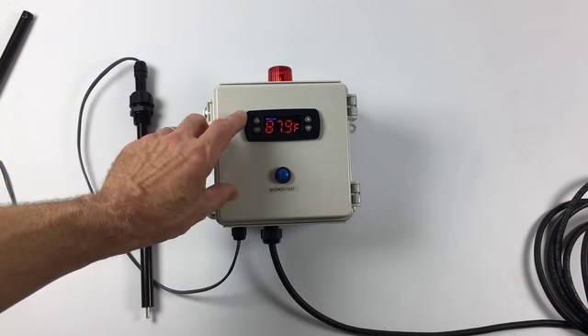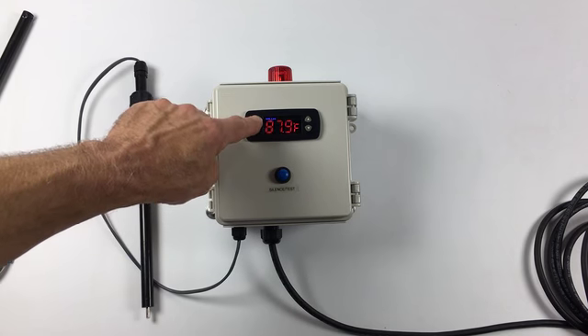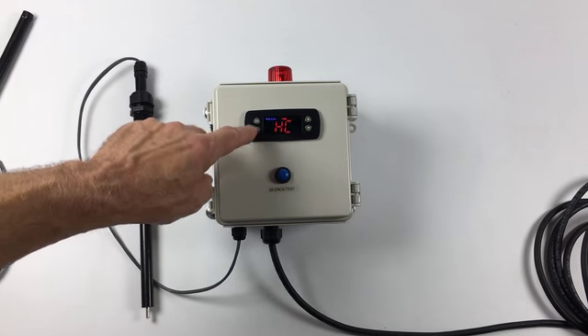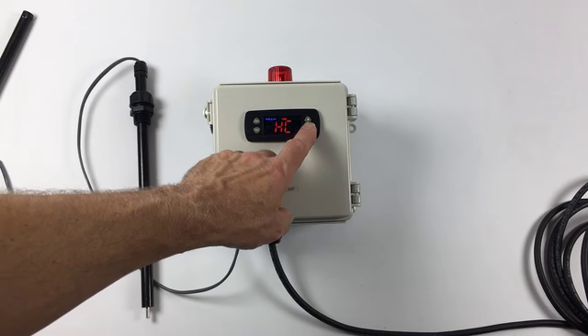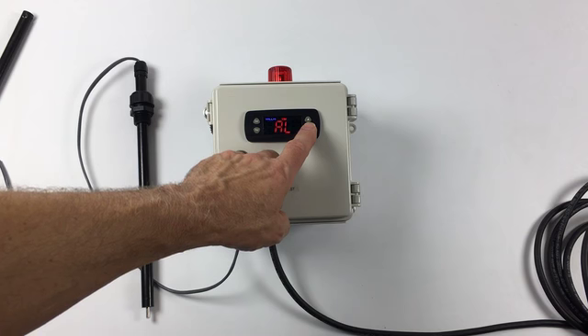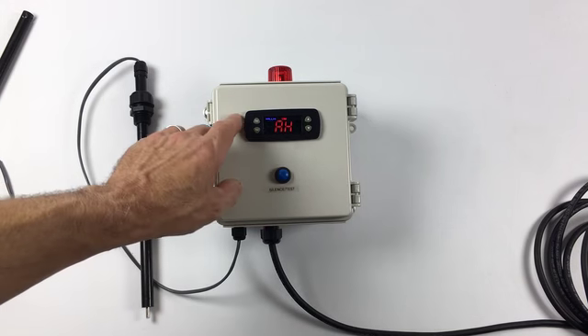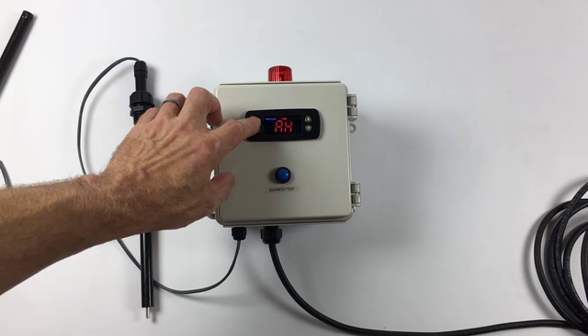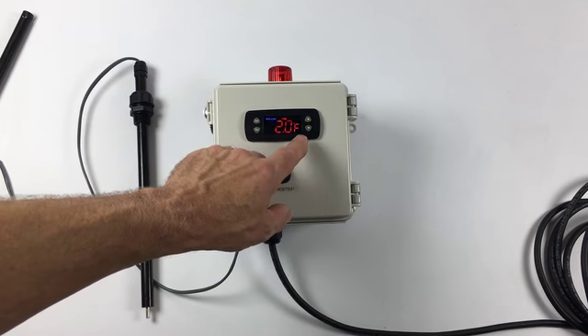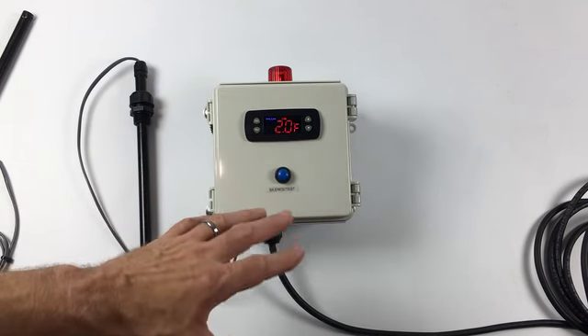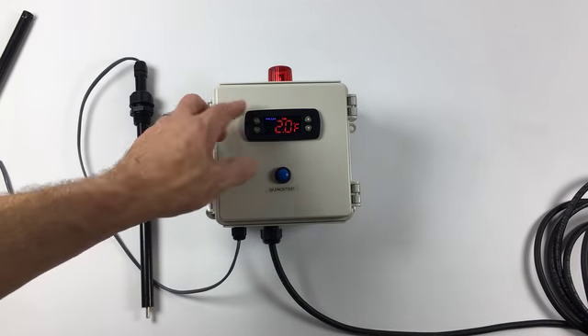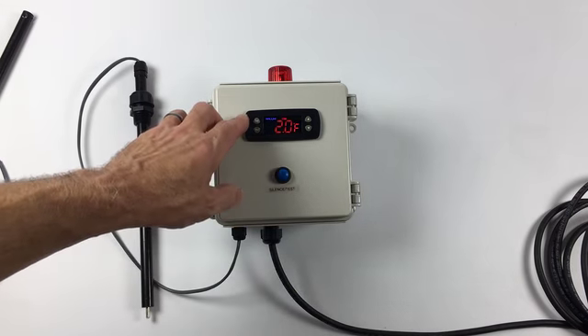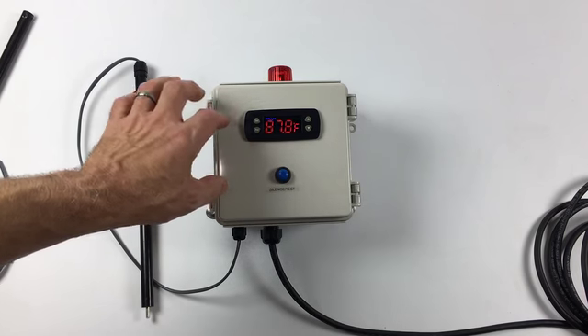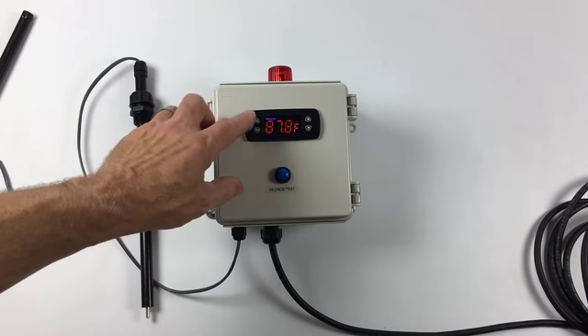Let me show you how to set that window. So here we hold down the set button for 3 seconds, and now we are into the sub menu, and it's very simple. There are only 7 options: heating and cooling mode, which we can disregard, the low alarm, the high alarm, so this is the one we're interested in. If we want to set that, there's the 2 degrees. That's the 2 degree range, basically. We can stray 2 degrees higher than the set point before we get an alarm. And same thing for the low set point. And that's really all you need to concern yourself with.